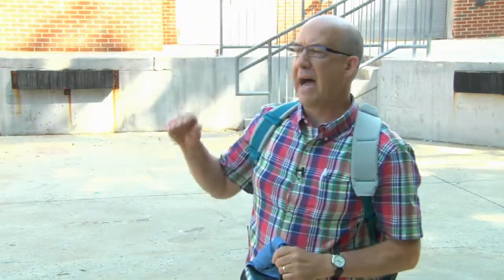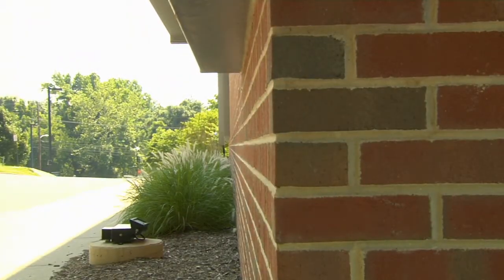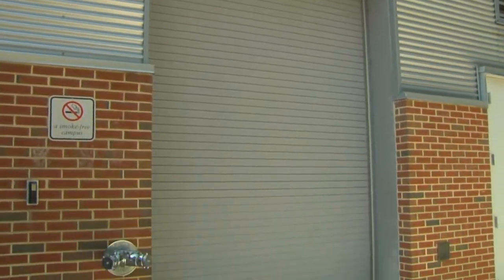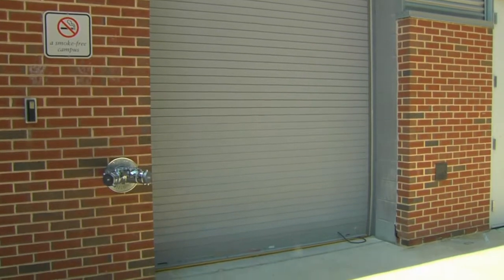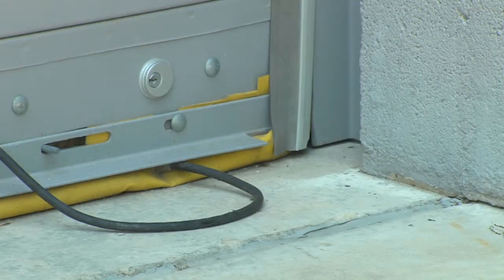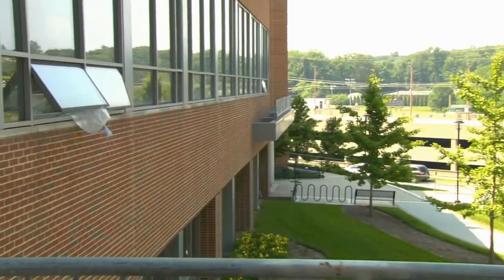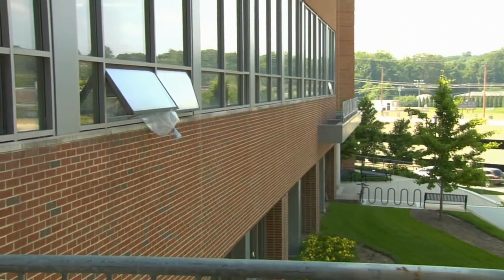The other thing that we're going to highlight is, we've already looked at the lights, but we've got a lot of outside lights. Right now, they all indicate they're off. That's good. We want to look at the doors, the roll-up doors, as I said earlier, not only to see if they're open, but how well are the seals on the edges, on the tops and bottoms of the doors. Is it an opportunity to improve the envelope? Operable windows, like we highlighted before, as we walk around, we want to see if there's any windows. Do we have any windows that are cracked?